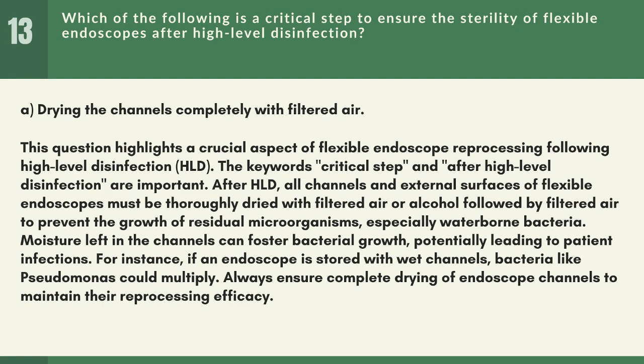Answer: A. Drying the channels completely with filtered air. This question highlights a crucial aspect of flexible endoscope reprocessing following high-level disinfection, HLD. The keywords critical step and after high-level disinfection are important. After HLD, all channels and external surfaces of flexible endoscopes must be thoroughly dried with filtered air or alcohol followed by filtered air to prevent the growth of residual microorganisms, especially waterborne bacteria.